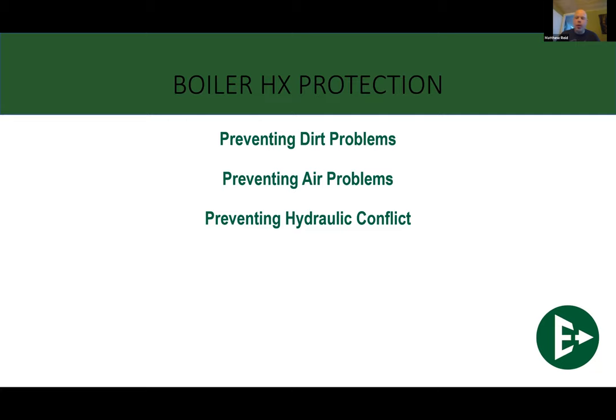And then we need to prevent hydraulic conflict, meaning that it needs to see flow. Lack of flow is going to kill a heat exchanger faster than anything. As that burner is on, with your 50 or 100 or 300,000 BTUs going through that burner, if we don't have water moving through that to take that heat away, that'll cause failures instantly. You will crack and split in a heartbeat if you don't have flow through these guys. A lot of these manufacturers now have built-in flow switches to make sure that they turn on, but not all, and especially not the mid-efficiency ones, the non-condensing. You don't usually see flow indicators on any of those residential models.